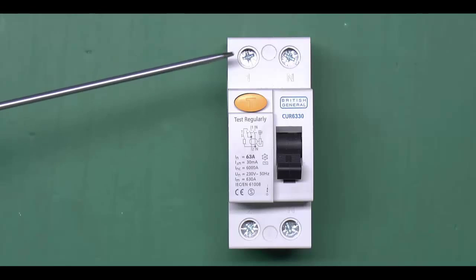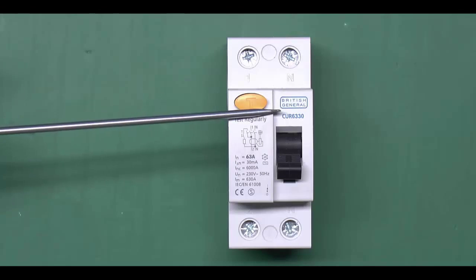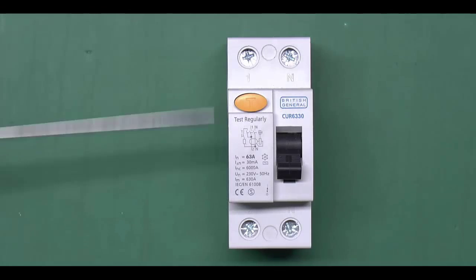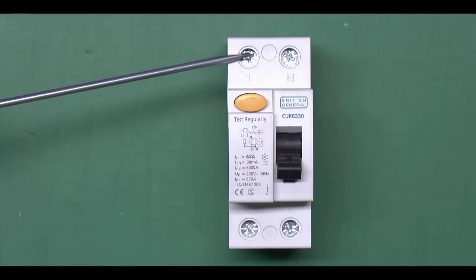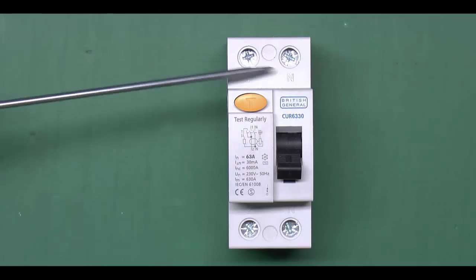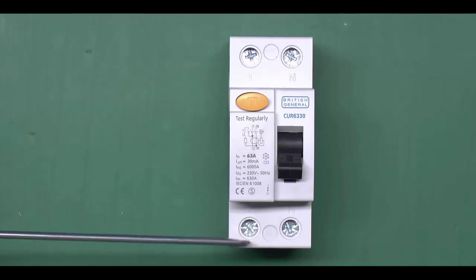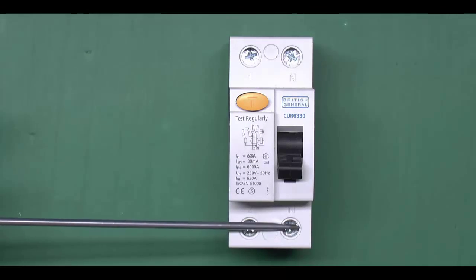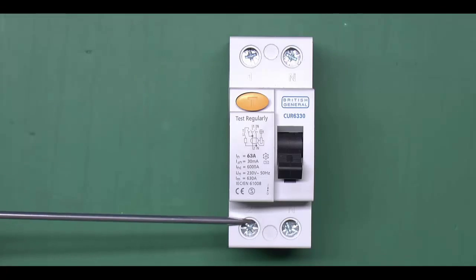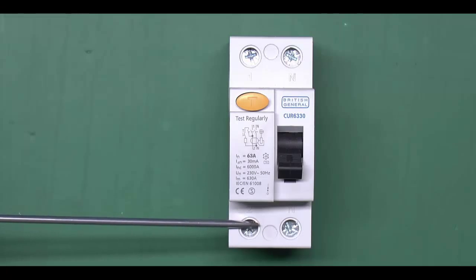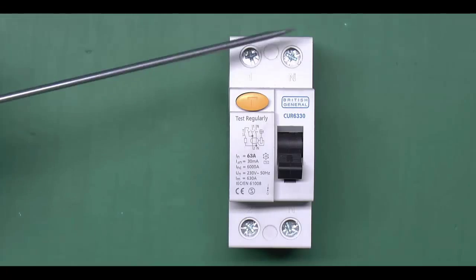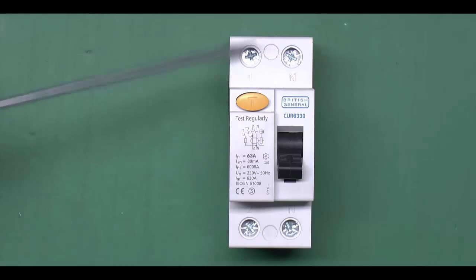Now here's a typical example. This particular one's made by British General, but they're all pretty much the same in design. You've got, in this case, two terminals at the top here for line and neutral, that's the supply in, and at the bottom line and neutral out. And these will always have a connection to both line and neutral, because they work by monitoring the current flowing through the device, so obviously through the line and then returning via the neutral.